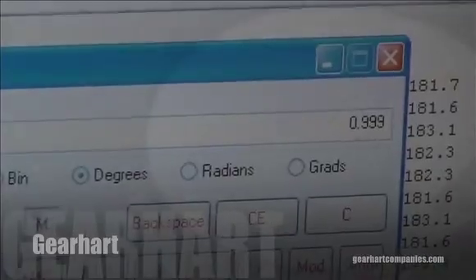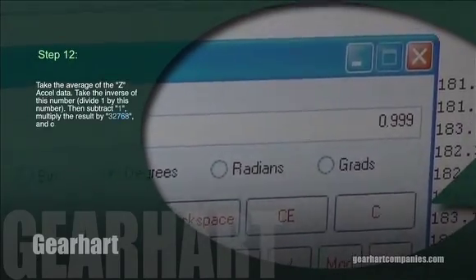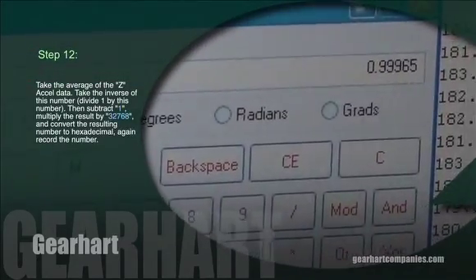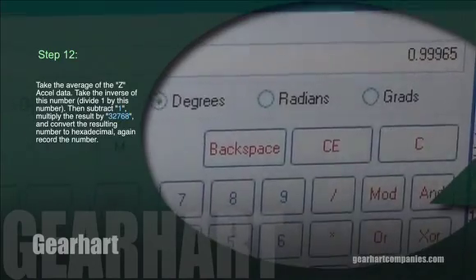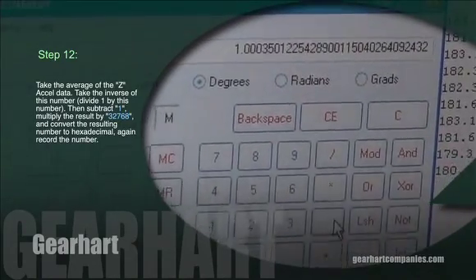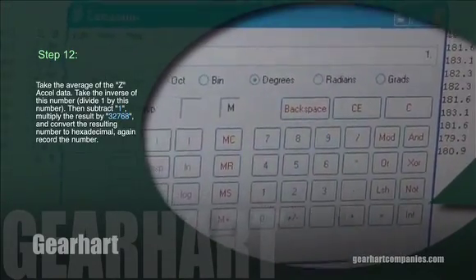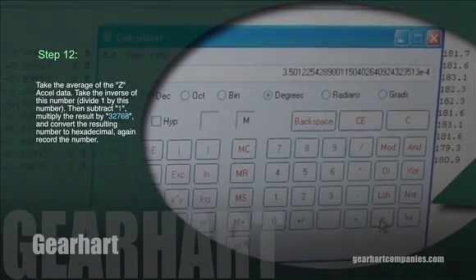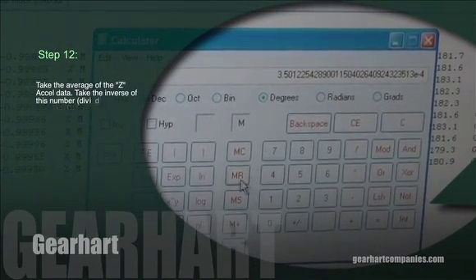Step 12. Take the average of the Z accel data. Then take the inverse of this number by dividing 1 by it, then subtract 1, multiply the result by 32,768, and convert the resulting number to hexadecimal, again recording this number.